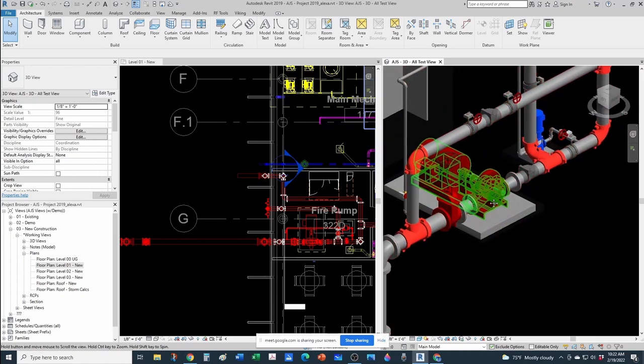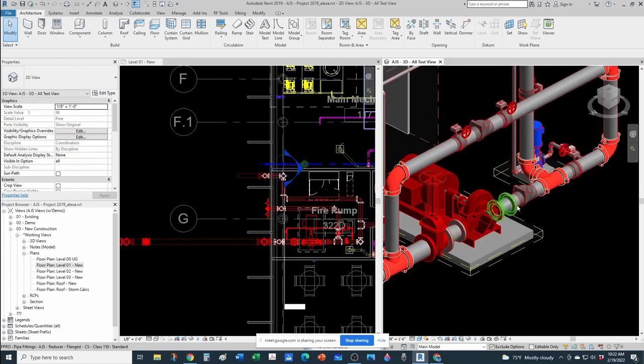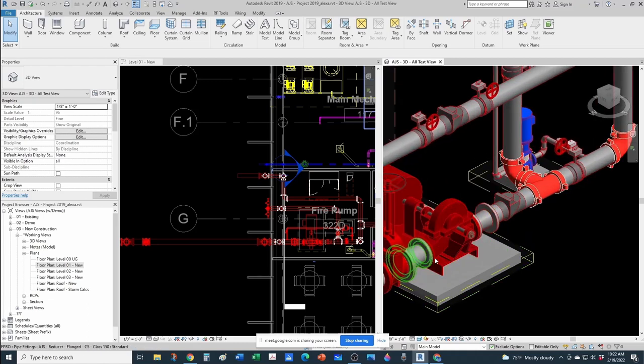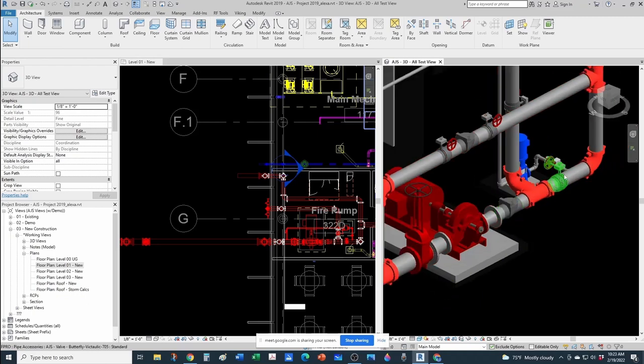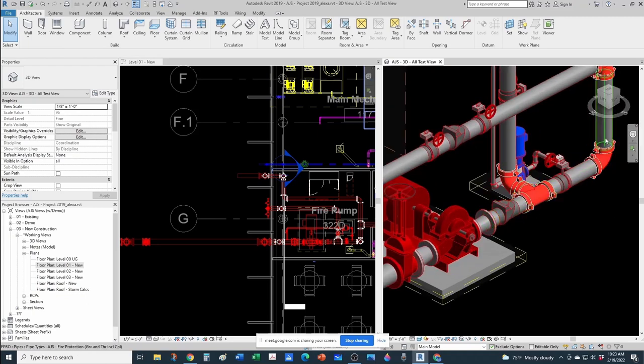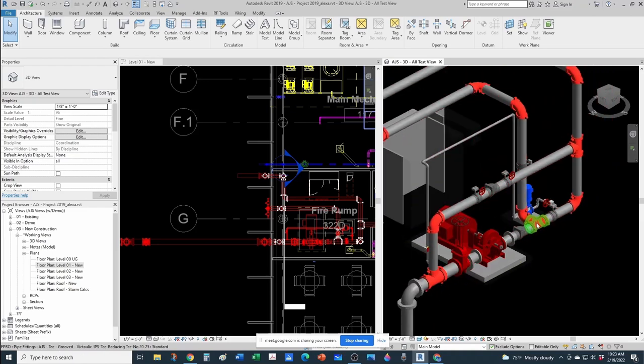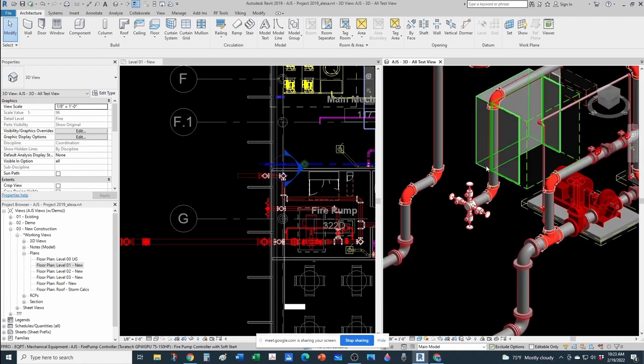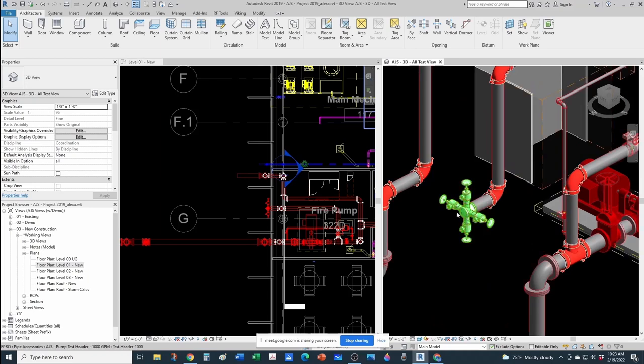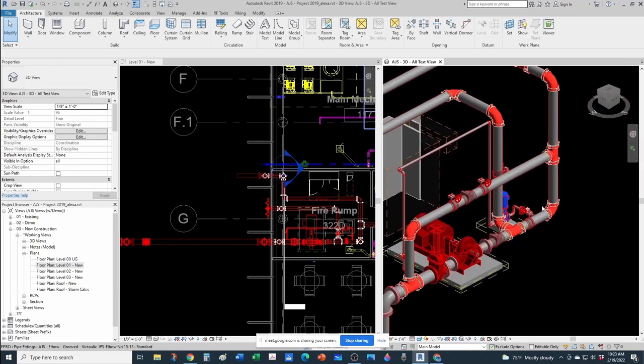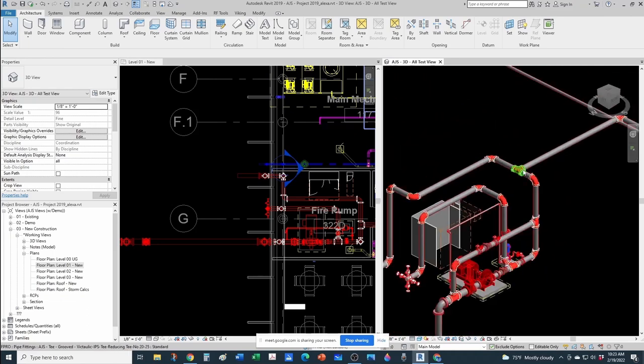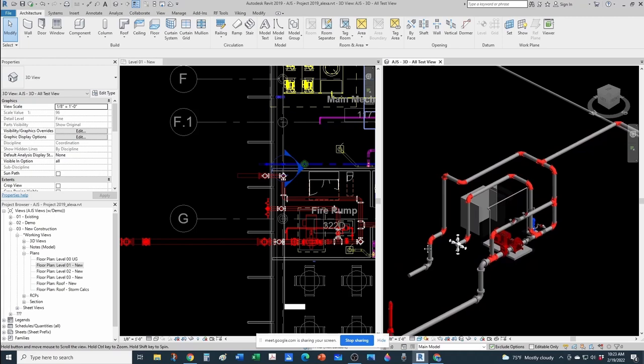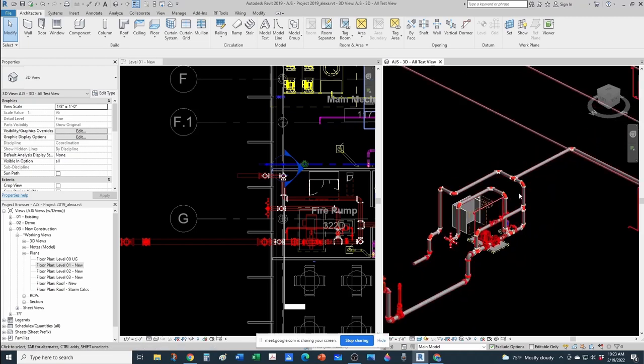That's our isolation valve right here. That's our reducer, our fire pump. Sometimes, depending on the suction size of the pump and the discharge, you may require a concentric increaser or not. Then that's our check valve to prevent backflow of the high pressure water. Then we have our takeoff to our pump test header right here, and then you go to the system, obviously connecting with a T to the line that is coming from the fire department connection.